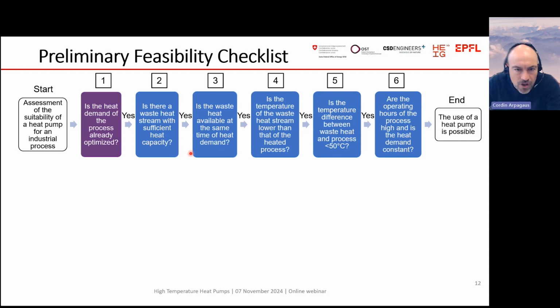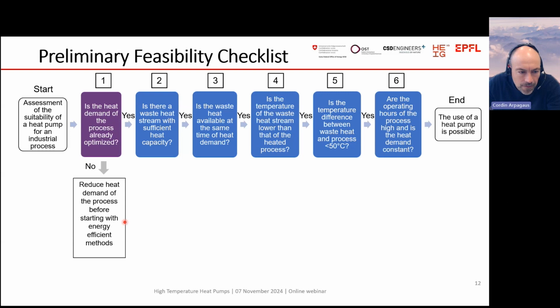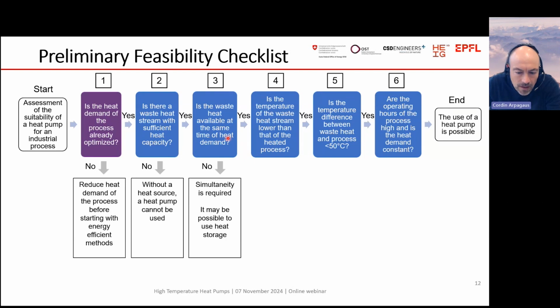And so we have a first check. When we go to an industrial company, we ask them some questions. Is there a heat demand, and is it already optimized? If yes, then we go to the next step. If not, then we would reduce the demand and try to do that first before going to energy efficiency measures. Then the second: is there a waste heat source available with a sufficient heating capacity? If not, without a heat source, a heat pump cannot be implemented. So it's very important that we have a heat source available. The third: is it available at the same time as the heat demand? If it's not simultaneously available, then we need some heat storage equipment.